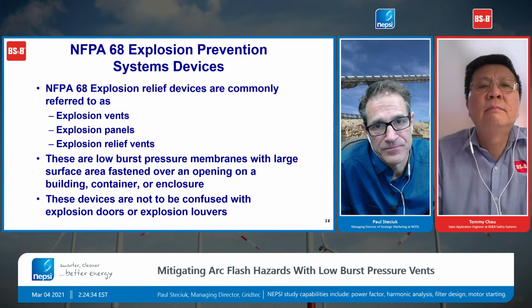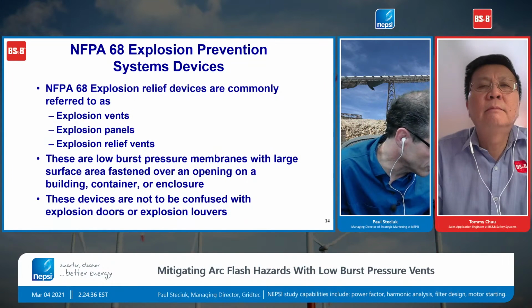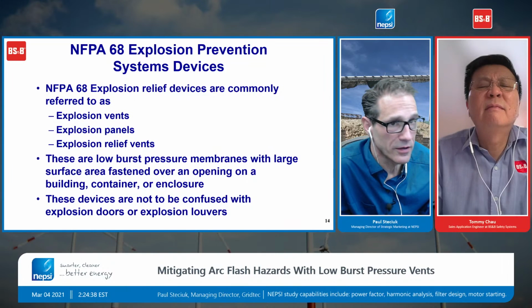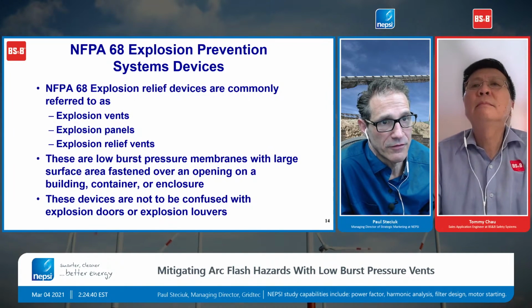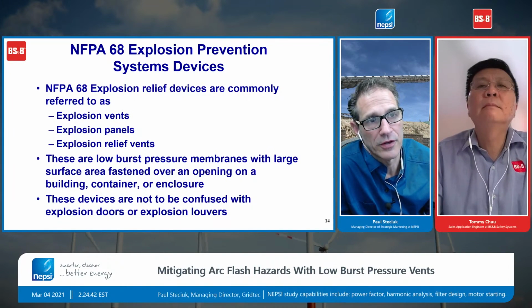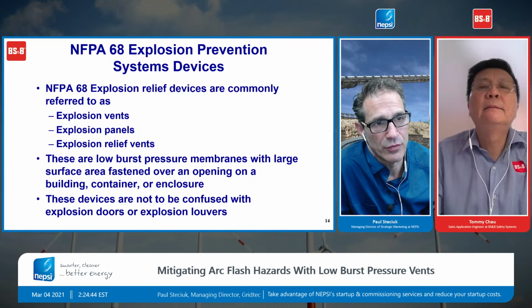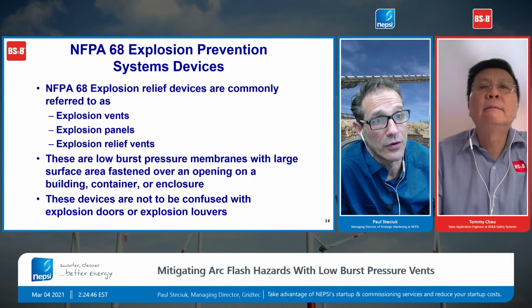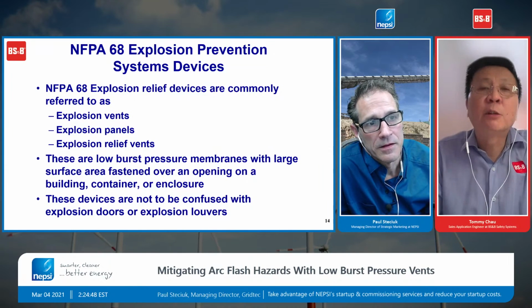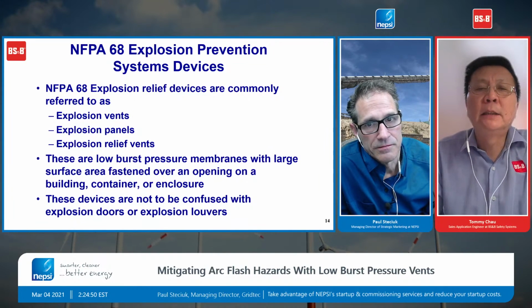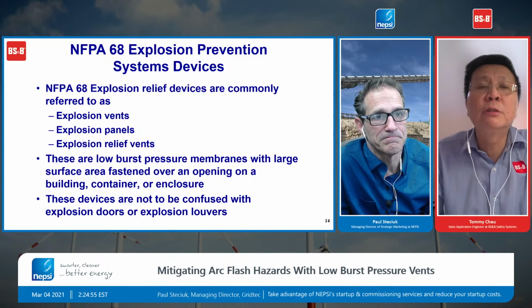Just to make sure we understand what you meant by that: when there is an arc flash event, you have to replace this membrane. This is a device that will need to be replaced afterward, correct? It's not a door. Correct. It's a one-use device. Yes. We would like to refer to them as non-reclosing devices.